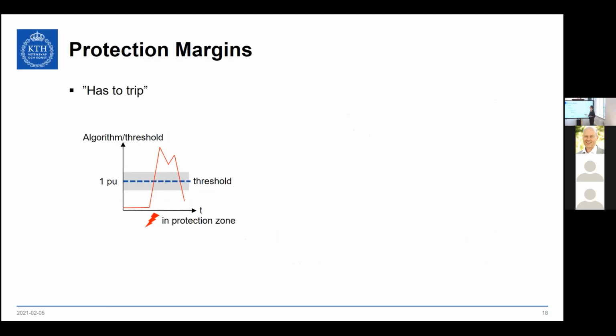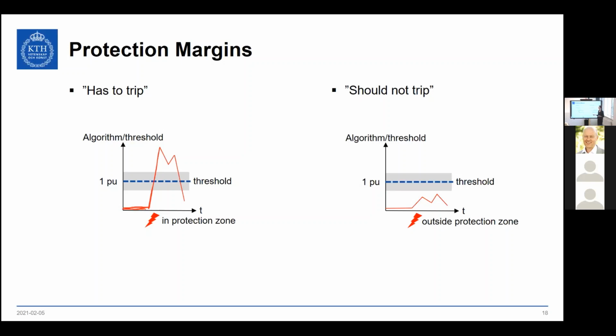So for every position in the grid that has to trip and has to detect a fault and open the circuit breakers to disconnect the faulty part, we have an algorithm, and here I divide by threshold, so I normalize, and then usually the algorithm output is close to 0, and then once a fault happens in the protection zone, this signal goes above threshold. So here the trip happens at 1 per unit because I normalized the threshold.